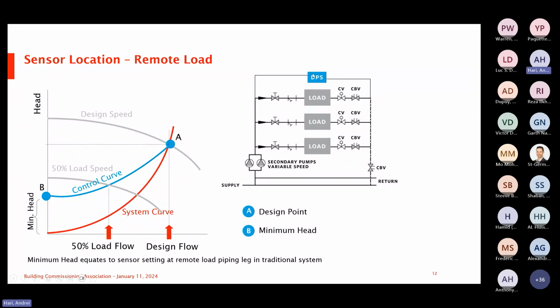My control curve, my DP sensor says I'm being satisfied, but this zone is not getting any flow because I'm not generating enough head to get to here. So what you need to do is start to move this line up, this control curve, which basically says that I'm moving the speed up until I have enough to get to that zone. And that's why in a lot of buildings, if there's a riser or a fan coil that's not being satisfied, it's typically one that has the lower flow. We're not generating the head pressure to get to that zone.